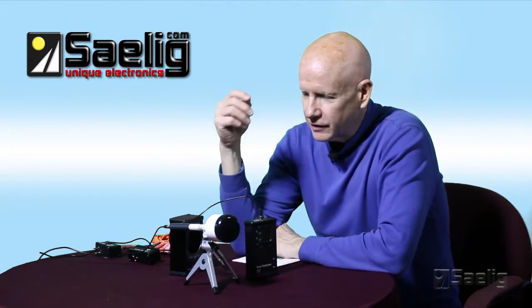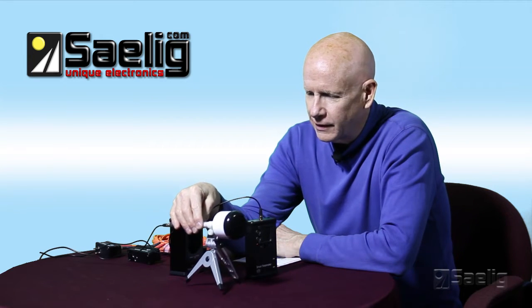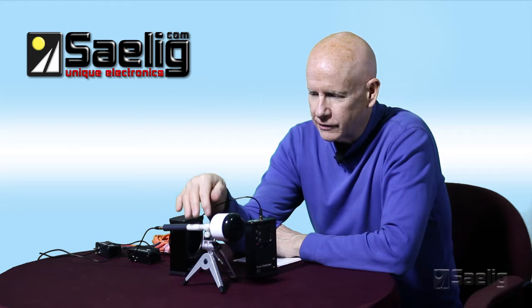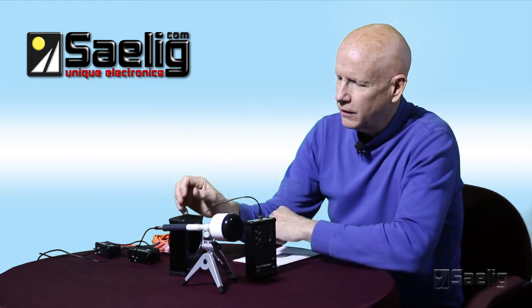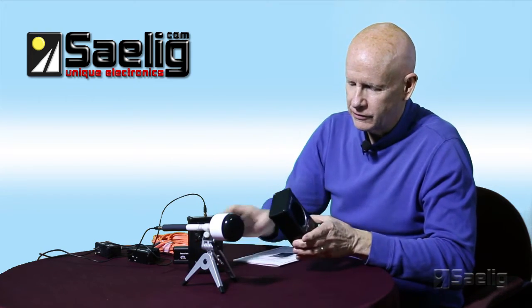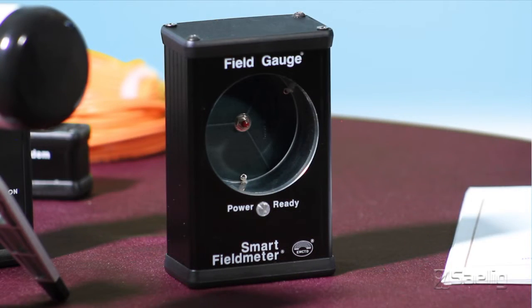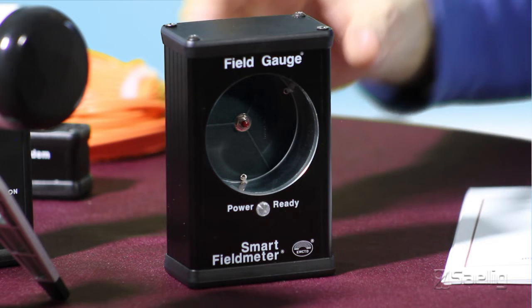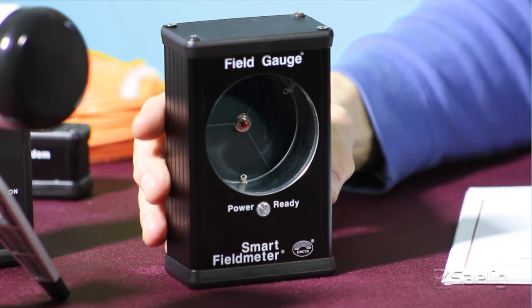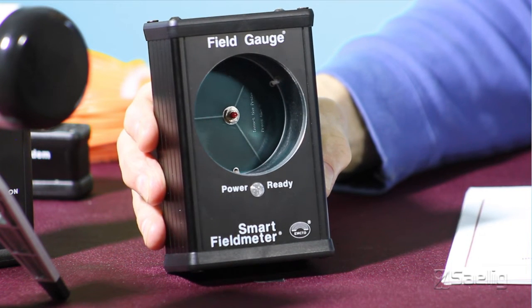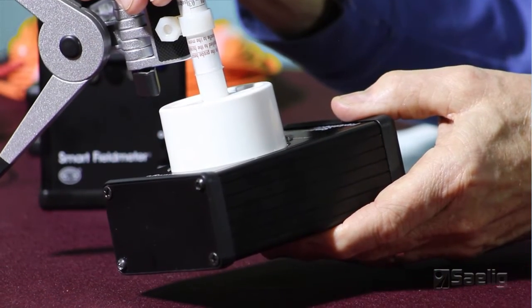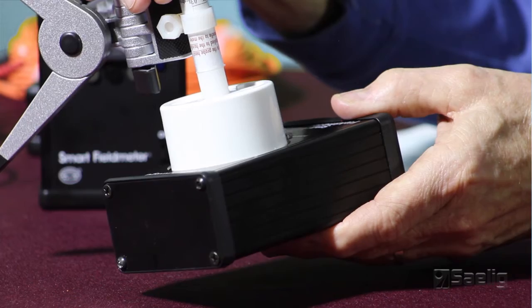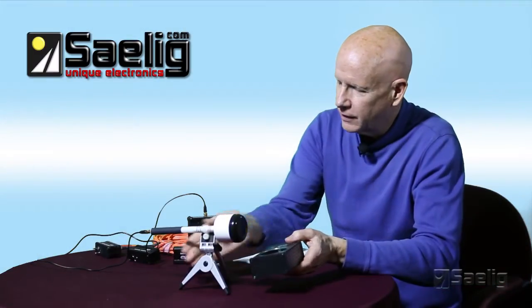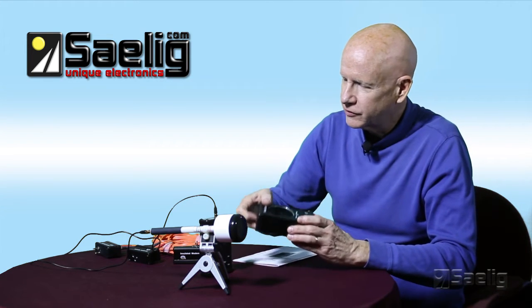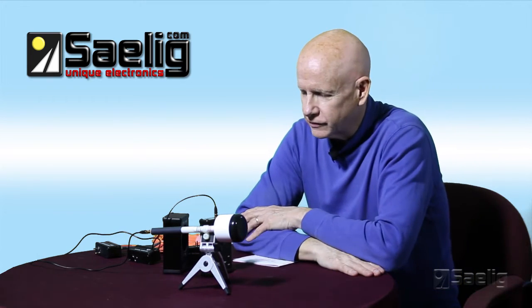This particular probe here is a 3 megahertz to 18 gigahertz model, and certain of the probes that they sell come with this other item here called the field gauge. The field gauge is a little go/no-go tester that you simply insert the probe itself right into here, and there's a little button in the bottom. You depress it, and this box generates a little electric field that this sensor can read and then display on the unit here. It's not a substitute for calibration, but you can use it just to make sure that your system is working out in the field if necessary.